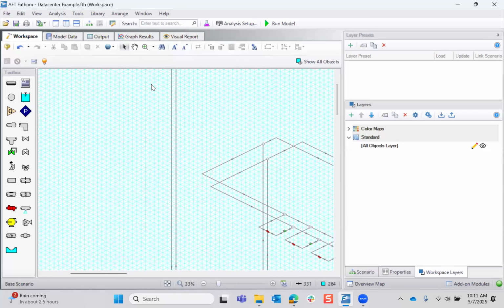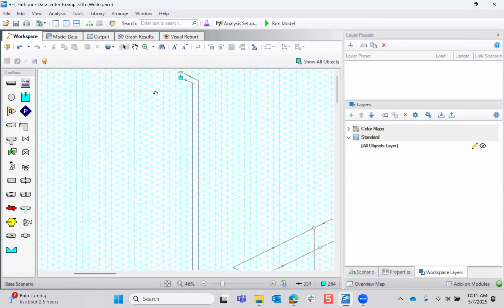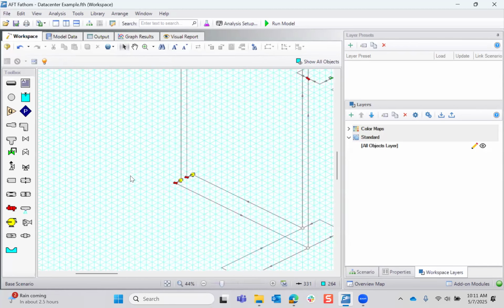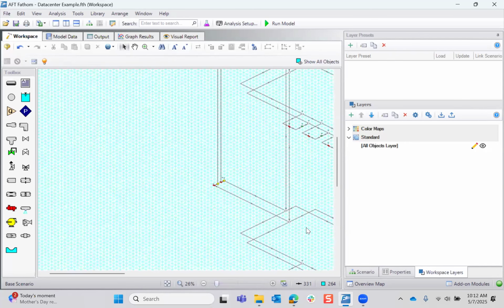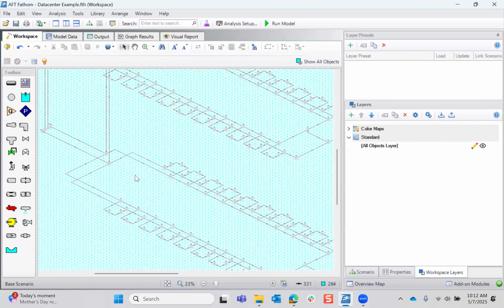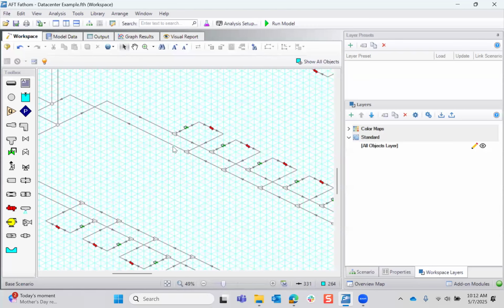So it kind of starts up at this top portion here, where I have built out a sort of cooling tower, where we're pulling in the water off of the cooling tower at about 80 degrees Fahrenheit, running it down to a chiller here at the bottom, which is cooling it down to about 40 degrees in this line. And then that's what's feeding the cold side of this data center.